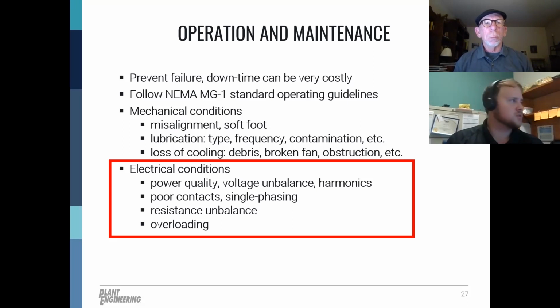Next, we go on to some of the electrical problems. So what can you do on the electrical side? Well, I like to keep the multimeter around. You can verify some phase-to-phase voltages. If you have an ammeter, you can check line currents. Sometimes you might not have access to these terminals, but if you do, check your phase-to-phase voltages with your multimeter. Check for balanced voltage.